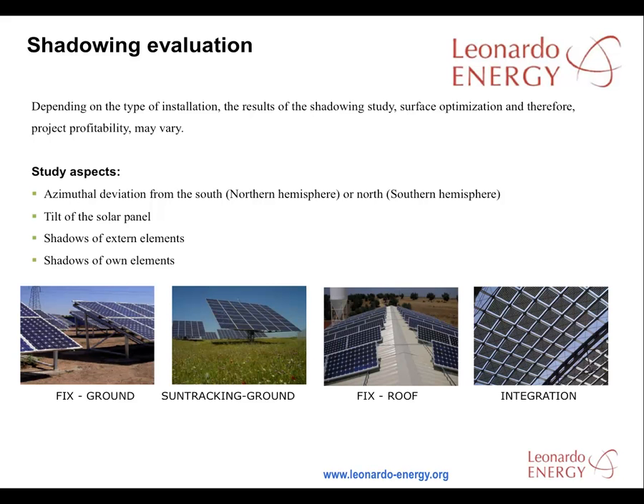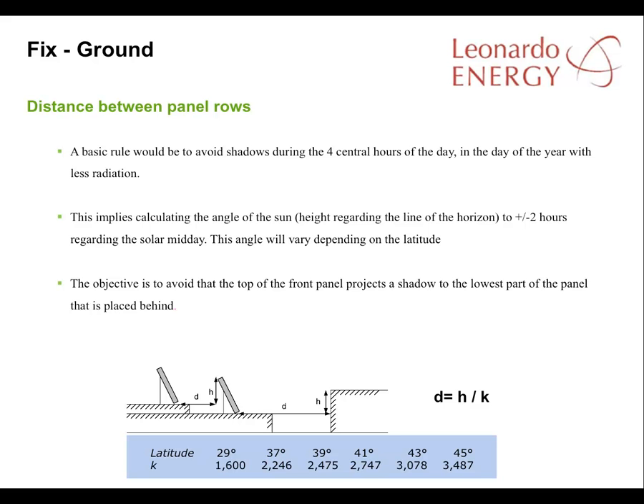Shadowing and surface optimisation can have considerable effect on the plant's profitability. The main aspects to consider are the azimuthal deviation from the south if the plant is in the northern hemisphere, or from the north if the plant is in the southern hemisphere, the tilt of the solar panels, shadows from external features, and shadows from features within the solar plant itself. A basic rule on optimal distancing between rows is to avoid shadows during the four central hours of the day, particularly during the times of the year when solar radiation is lowest.